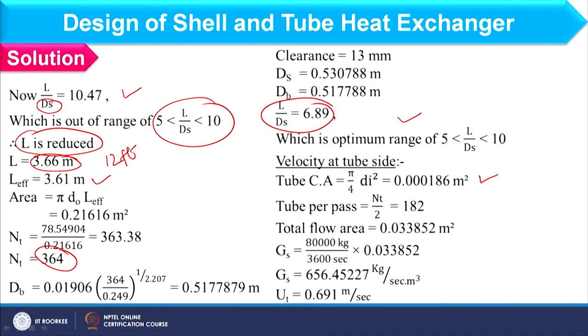The dirt factor for toluene will be the same as benzene from the previous example in Lecture 15. Here, water is on the tube side and toluene is on the shell side. Let us continue with the velocity calculation on the tube side. The cross-sectional area per tube and total flow area are calculated, and since we are considering two tube passes, the velocity comes as 0.691 m/s.